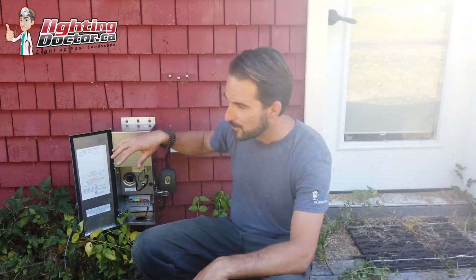But you can run 100 watts of lights on 300 feet of 12-2 cable without having significant enough voltage drop to affect those lights. For example, on this one, we easily ran about 350 feet of cable way out there. We started on our 15 volt tap and we have no issues with lighting. On this entire project, we probably ran over 2,000 feet of 12-2 low voltage direct burial cable.